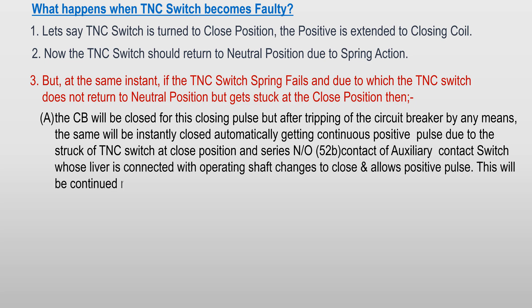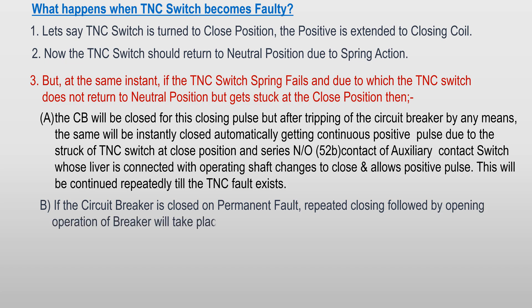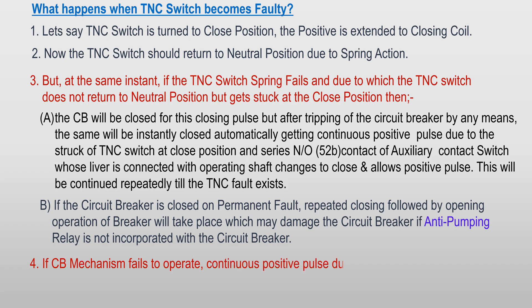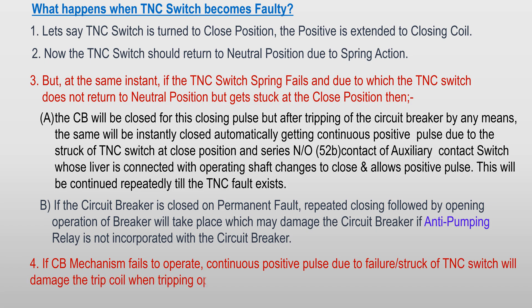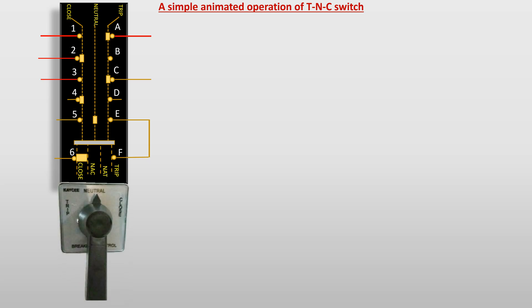This will be continued repeatedly until the TNC fault is corrected. If the circuit breaker is closed on a permanent fault, repeated closing followed by opening operations will take place, which may damage the circuit breaker if an anti-pumping relay is not incorporated. If the circuit breaker mechanism fails to operate, a continuous positive pulse due to the stuck TNC switch will damage the trip coil when a tripping operation is attempted. Please watch the operations by the TNC switch to get a clear understanding of switching of the circuit breaker.